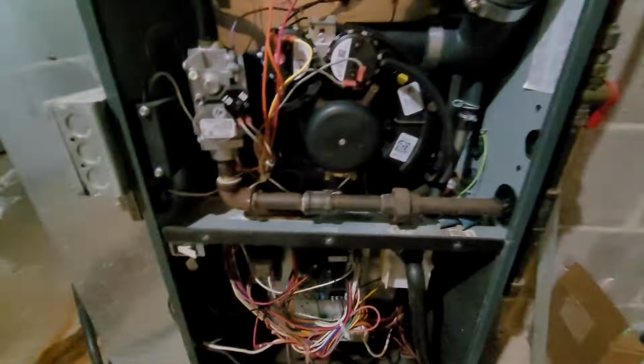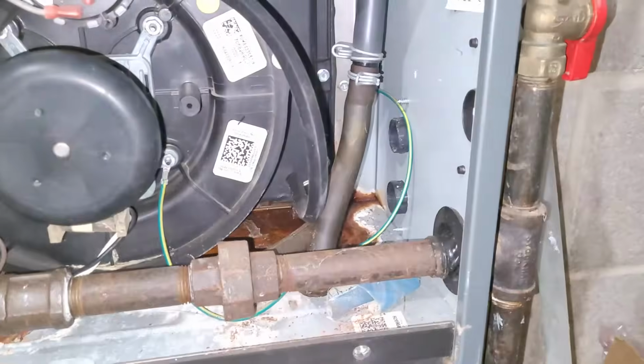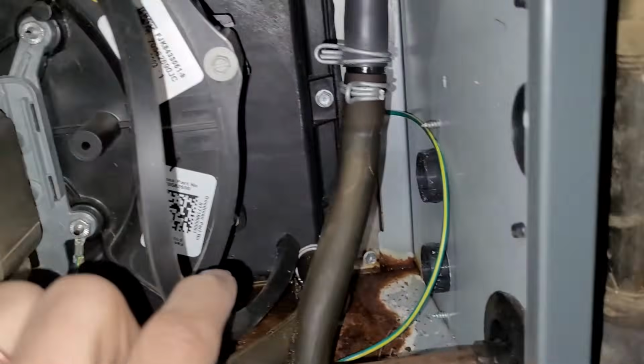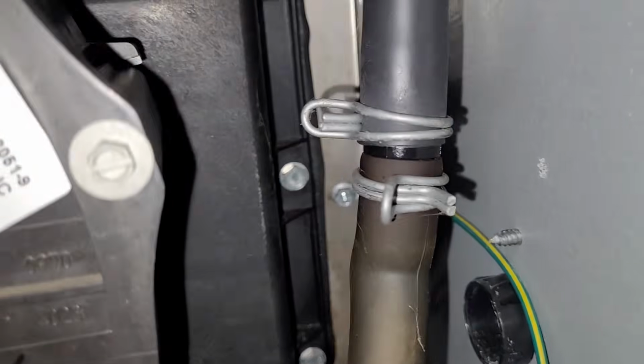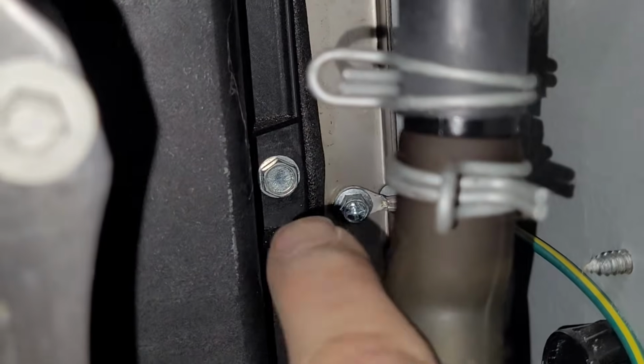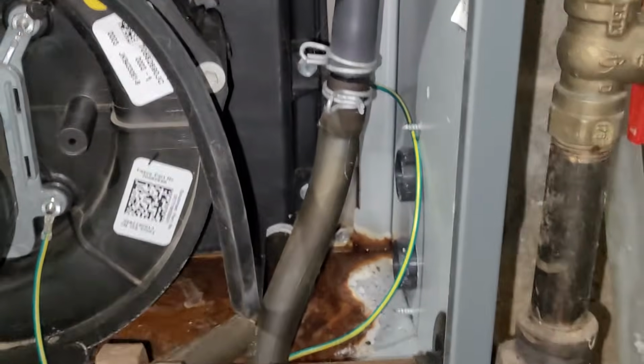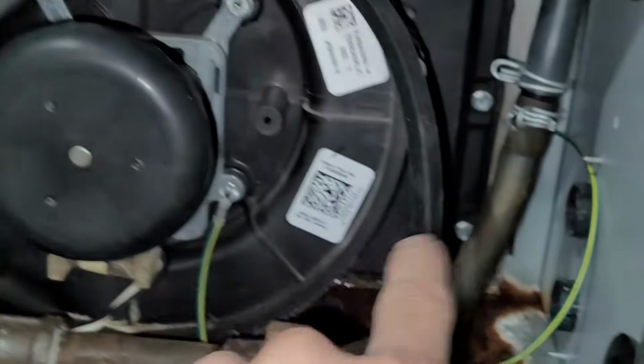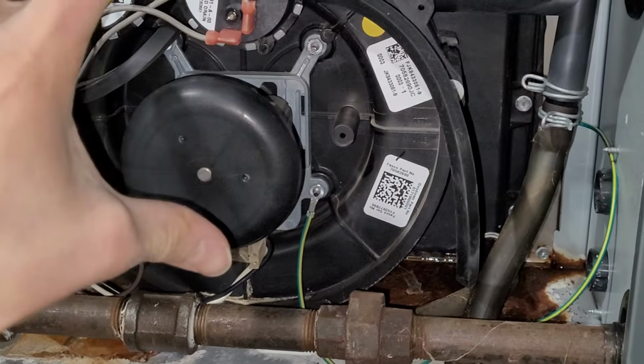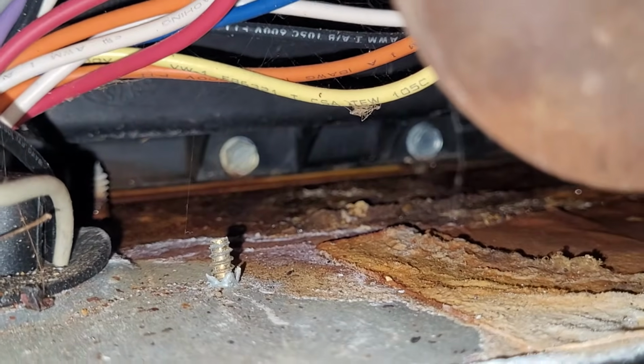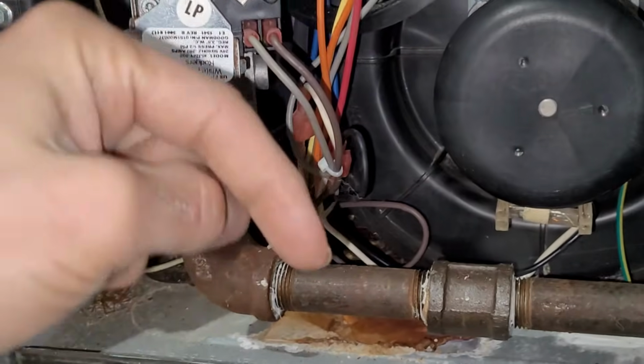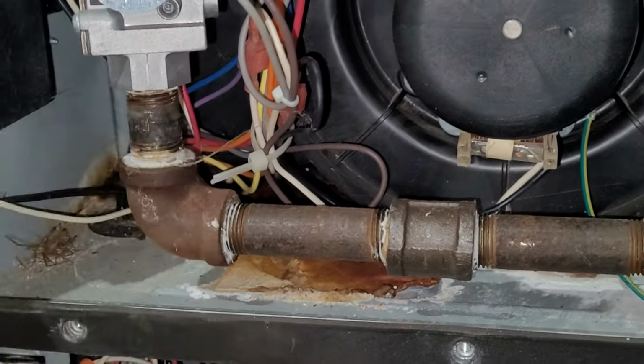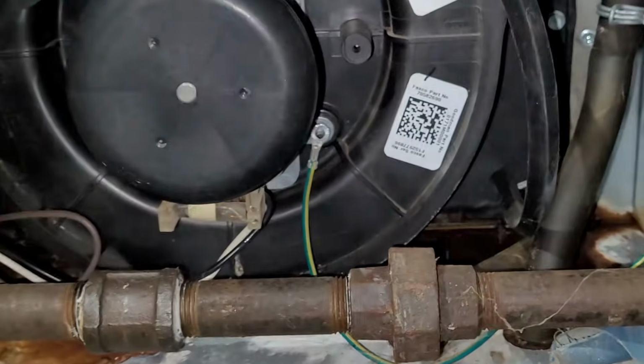So in this case, like I said, I was going to talk more about where we actually have it leaking. This is a pretty common thing I see on these Goodman furnaces. There's a foam gasket right here, and they just don't seal super great. So we're going to actually be replacing that foam gasket. We'll have to pull a bunch of this stuff out of here so that we can get at it, remove all the 5/16 screws around the bottom, and replace that gasket. I will link in the description of this video to the video about actually replacing that gasket.